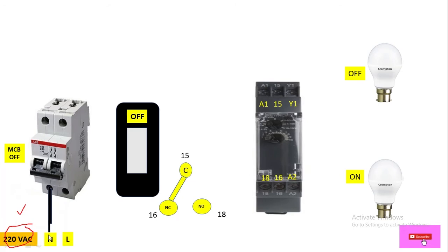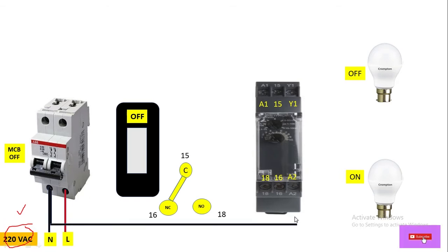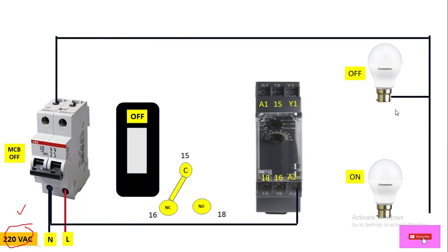From the supply, let's connect neutral to the input terminal of the double-pole MCB, and the live phase terminal is connected to the other input terminal. Now let's complete neutral wiring first. From the MCB output, connect neutral to the A2 terminal of the timer — the black wire is neutral. Also run neutral supply to the two loads, which are AC-operated lamps or LED bulbs.